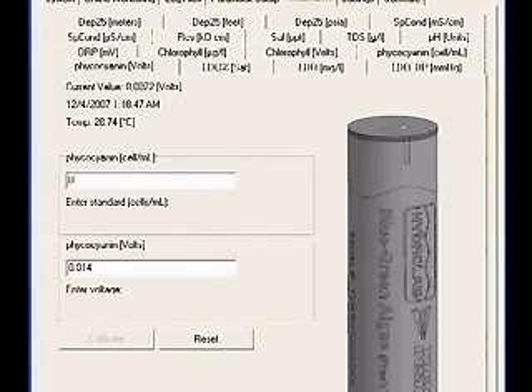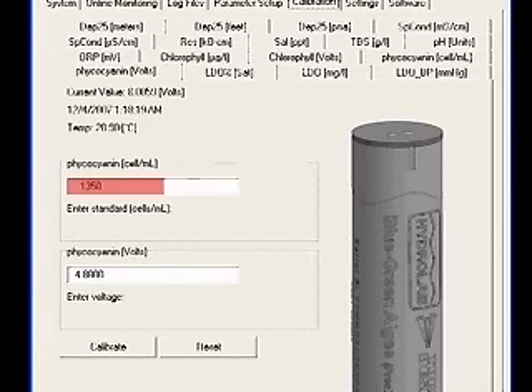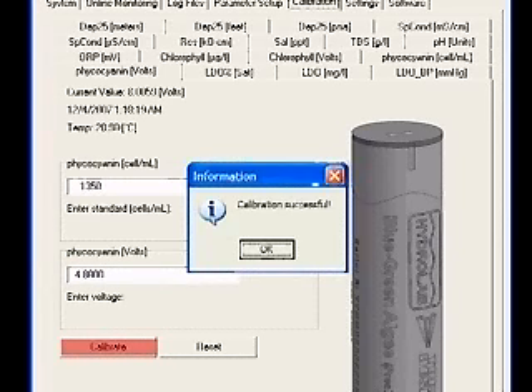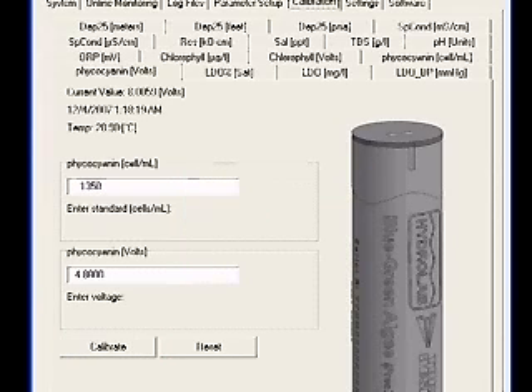Now type the extracted value into the box labeled phycocyanin cells per milliliter or phycoerythrin cells per milliliter. Type the voltage recorded from the sample before it was extracted into the box labeled phycocyanin volts or phycoerythrin volts. Click the Calibrate button. A calibration successful message will appear. These concentrations and voltages can be used for future calibrations of this specific blue-green algae sensor. The blue-green algae sensor is now calibrated.